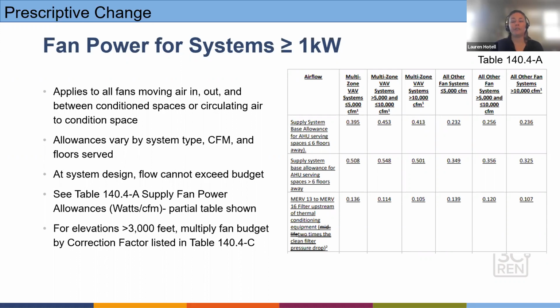For elevations greater than 3,000 feet, you need to multiply the fan budget by the correction factor listed in table 140.4-C. So take a look at that. And again, at system design, flow cannot exceed budget. So make sure you're keeping an eye on that.